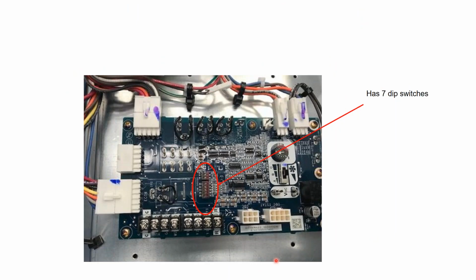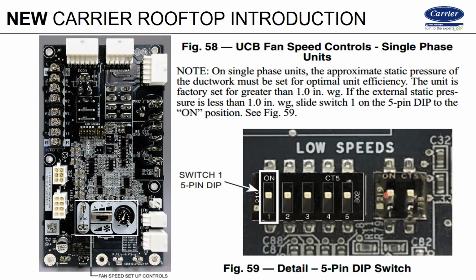Again, the 3-phase board will have just 2 dip switches, these 2 here, and they'll actually be perpendicular to this. The single phase has the additional 5, and that's what we're going to get into today and talk about how to set these up. So on a single phase unit, we're going to do the same thing with dip switch 1 that we would do on a 3-phase unit with just the 2 dip switches.